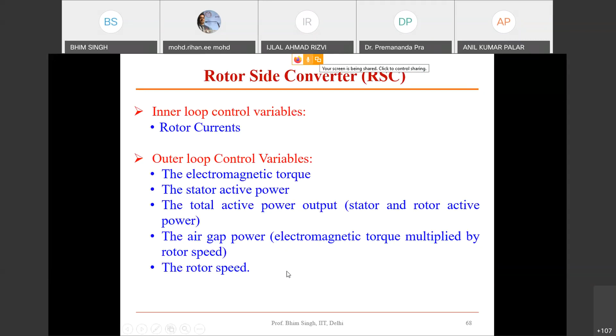I told you torque and active power, all those are for maximum power tracking, for the rotor speed control. And I told you that you have a P regulator for rotor side control, that is for MPPT. By controlling the speed of your rotor, you may not be sensing the rotor speed, you might be estimating the speed, and you might be doing MPPT by this. So that is your vector control. Quadrature axis current means the torque producing component, and the flux producing component is for reactive power, set to 0 on the stator side, that is for reactive power control. Then you have a rotor side current controller, and finally it comes out as a voltage. Current control gives you the voltage control, because you are not operating the converter at a very high frequency. I told you 1.8 kilohertz.